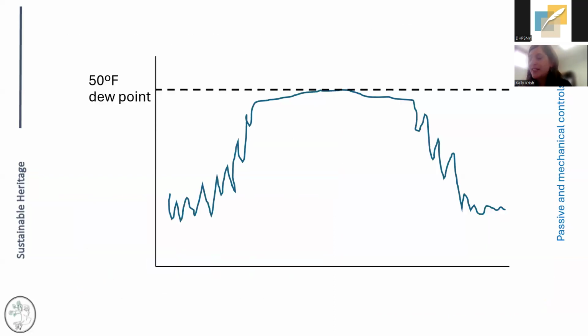Okay, sorry. I know this is a lot. I'm hoping I'm not going too fast, but with this graph, what I wanted to convey was we talked about that 50-degree dew point being sort of a default for a lot of mechanical systems. And I wanted to put it in your mind that if your cooling coil and chilled water are capable of a 50-degree dew point, that equates to a 70-degree, 50% RH environment.